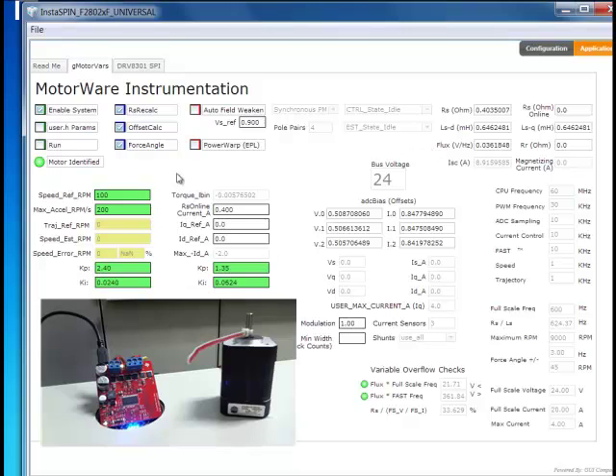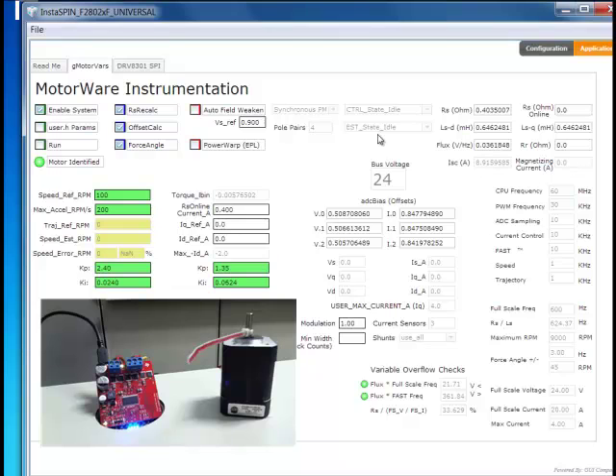So our motor identified light has come on. That means that the state machine has finished without an error. It doesn't mean that your parameters are necessarily correct. So in the quick start guide, I go through some sanity checking of the parameters to see if they make sense.